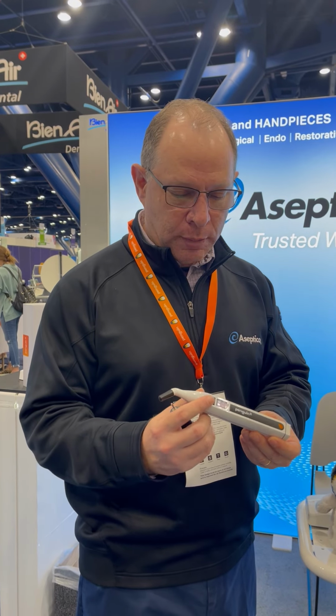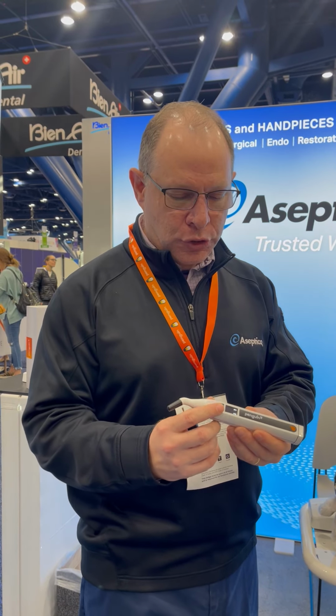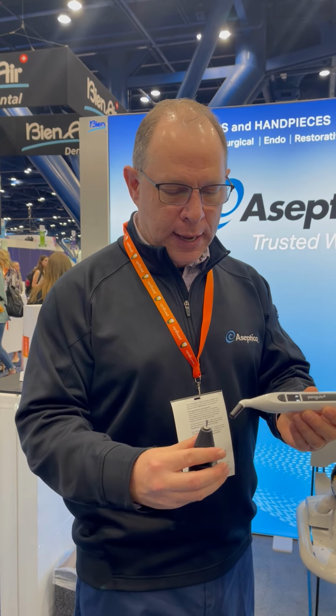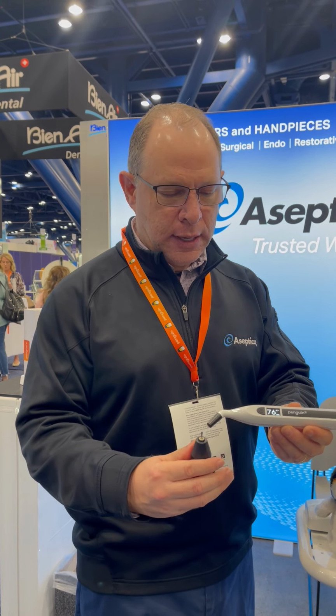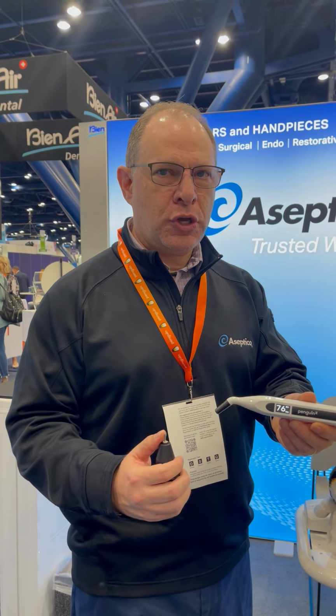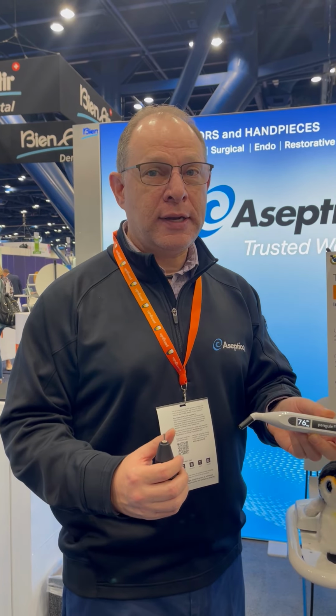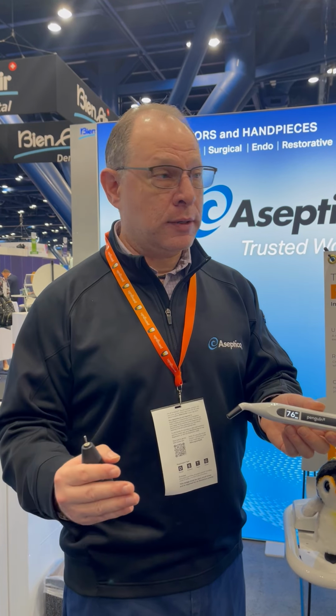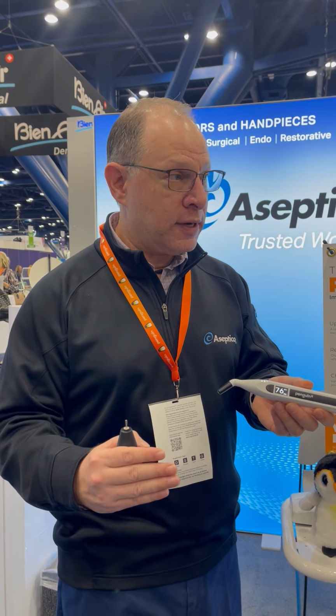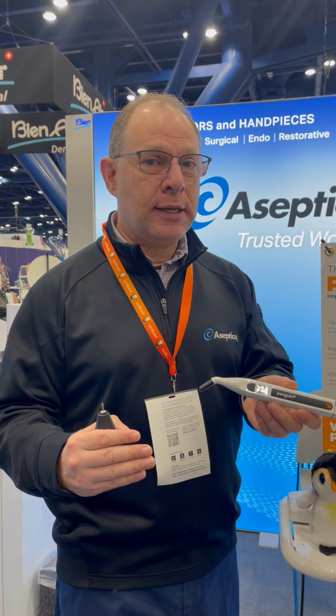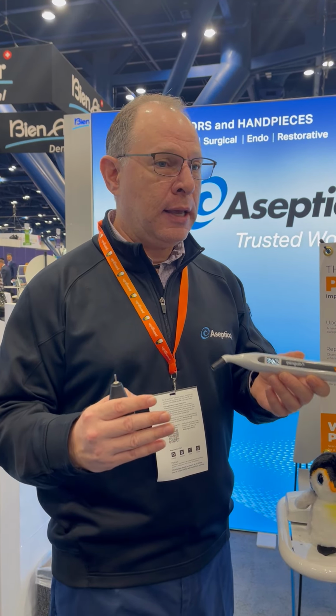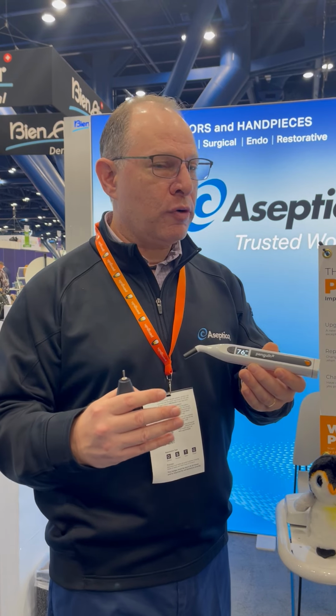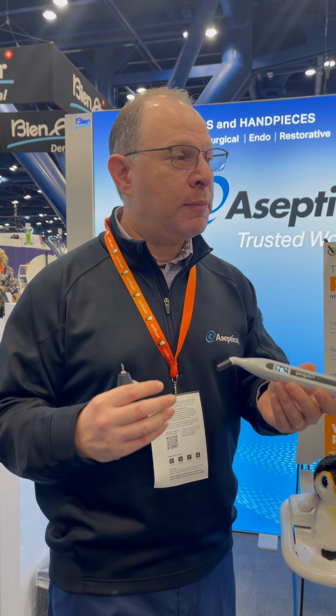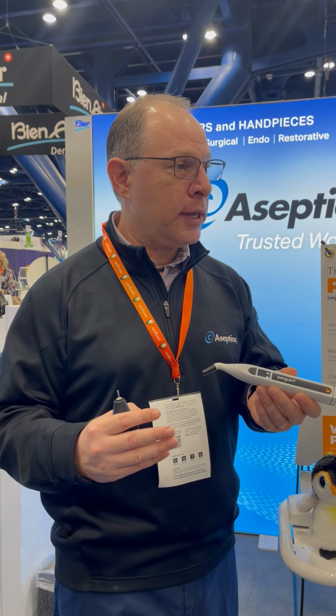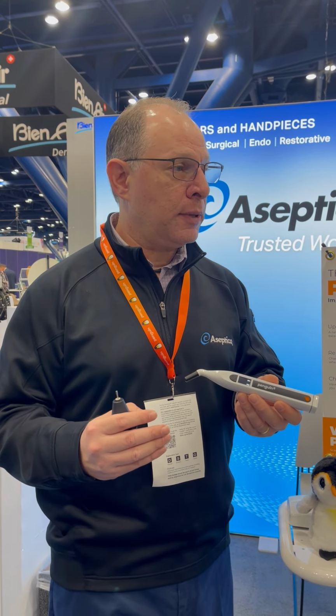So you have a power button here that you turn on. It shows the software version, and then in a matter of seconds, it will show you your ISQ number. An ISQ of 76 can be immediate loaded. If it's below 70, the best practice is to let the implant heal or osseointegrate over 3 or 4 months, measure again, and depending on where you are on the ISQ scale, you may determine whether that's the point to restore an implant or not.